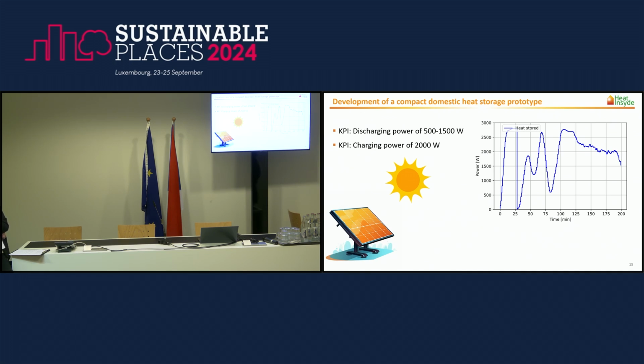What's really crucial, because when you start charging, we need to have a temperature difference of about 60 degrees to effectively charge the battery. And the first 5 minutes, I don't have that. I need to heat up my system a bit and get the heat in there, and then we can start really charging the battery. What's really detrimental is if I can heat my battery to the point where I can charge, and then I stop for 4 hours, and then I do it again, and I stop. Then, at that point, you're not effectively charging the battery, but that doesn't really happen that often in real cases, unless you can predict it, like, okay, if I start charging at 6 p.m., I know I'm not going to finish, so best not.